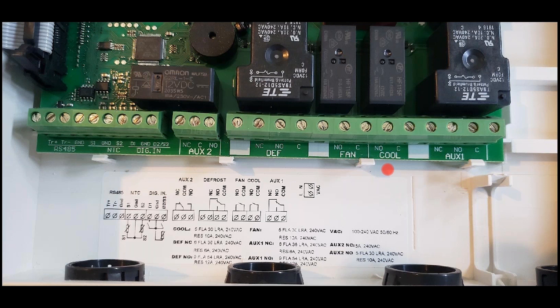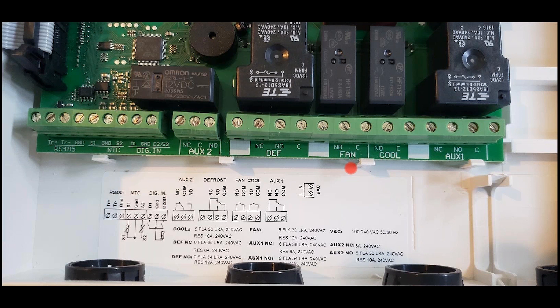Next we have fan. This is actually the evaporator fans, so the evaporator fans generally run when the compressor is on and, depending on the type of defrost you have, can either be on or off during defrost and when the system is not calling for cooling. In an off-cycle defrost, we generally leave the fans running when the system is off because we use the space air to defrost the evaporator during the off cycle.